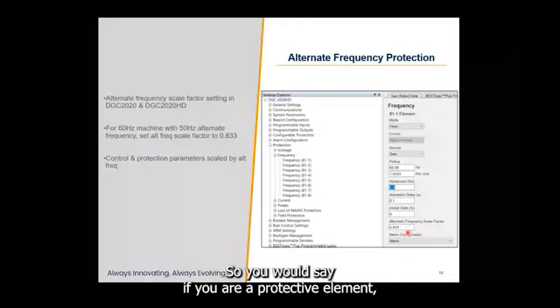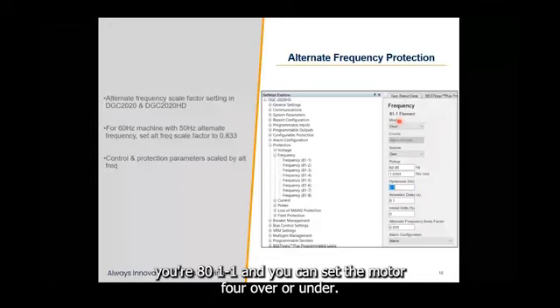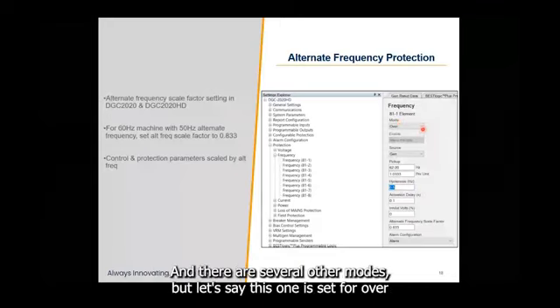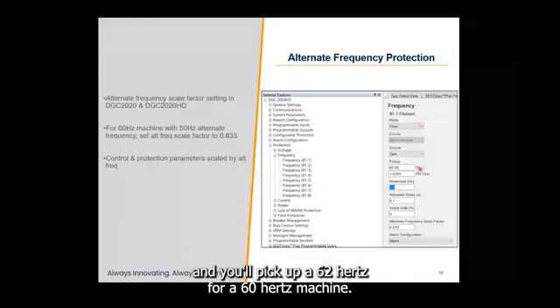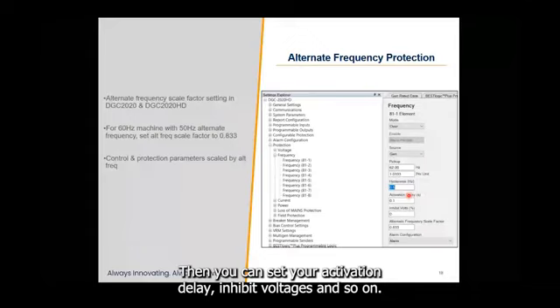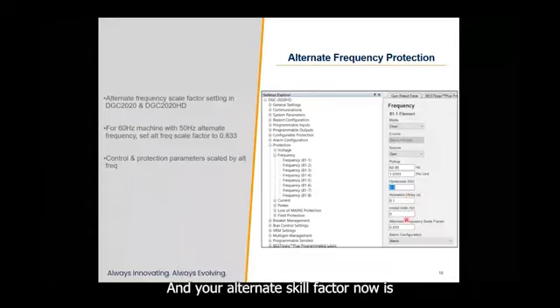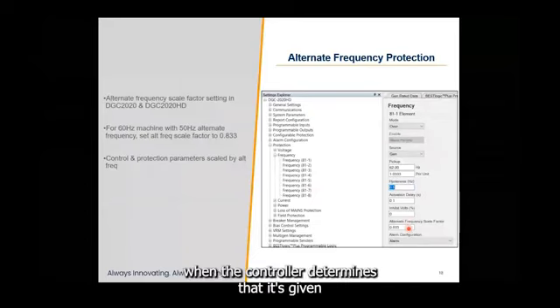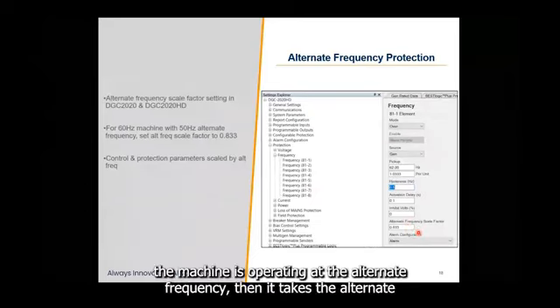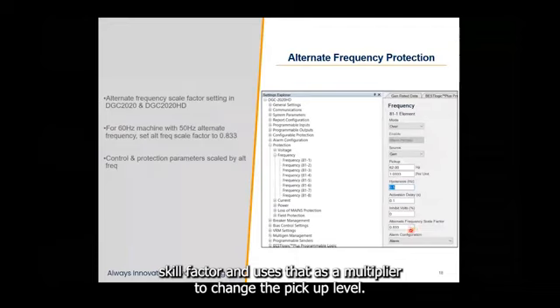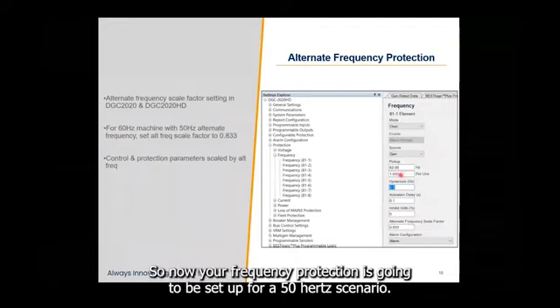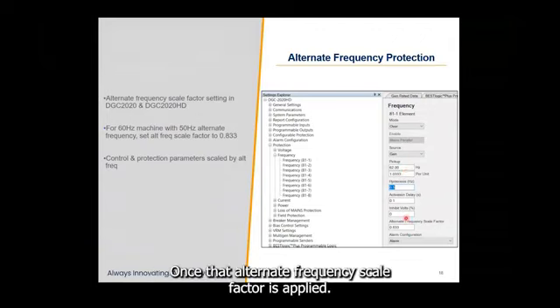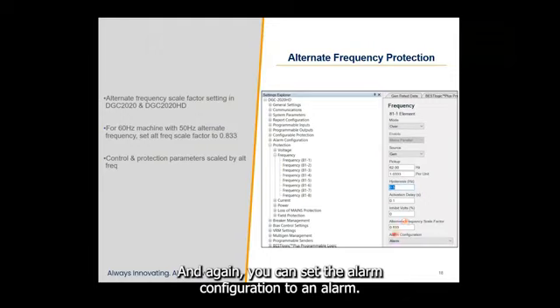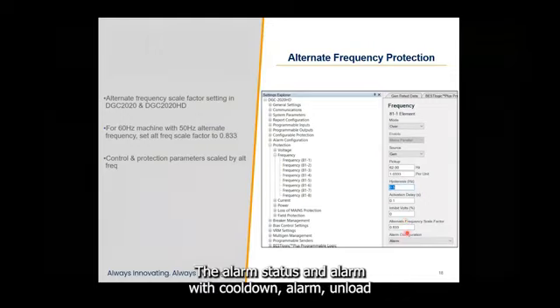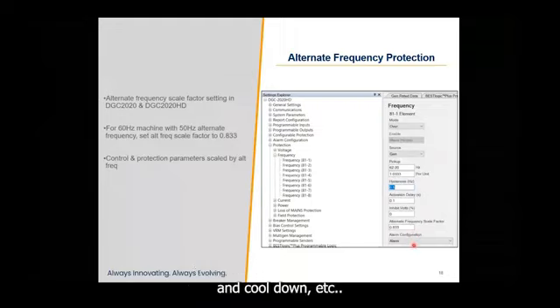So you would set your protective element, your 81-1, and you can set the mode for over or under, and there are several other modes. But let's say this one is set for over, and your pickup is 62 hertz for a 60 hertz machine. And then you can set your activation delay, inhibit voltages, and so on. And your alternate scale factor now is when the controller determines that the machine is operating at the alternate frequency, then it takes the alternate scale factor and uses that as a multiplier to change the pickup level. So now your frequency protection is going to be set up for a 50 hertz scenario once that alternate frequency scale factor is applied. And again, you can set the alarm configuration to an alarm, a pre-alarm, a status, an alarm with cooldown, alarm with unload and cooldown, etc.